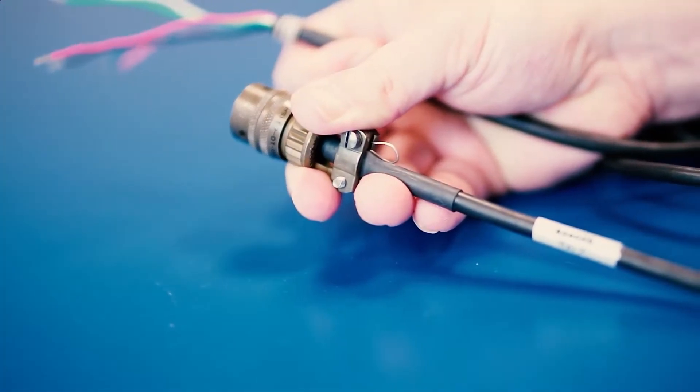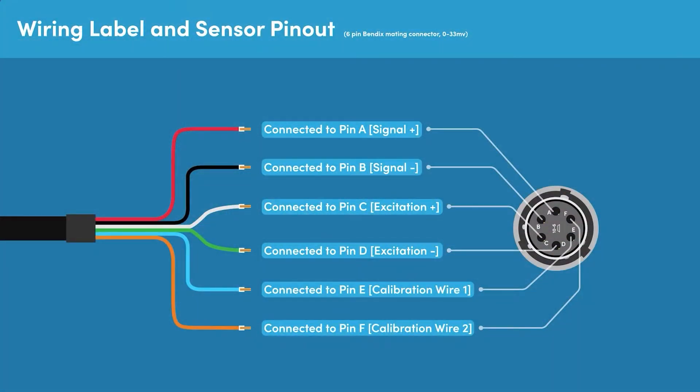The standard connection pinout for a cable used with a pressure sensor that has a 0 to 33.3 millivolt output would be as follows. The red wire is connected to pin A and is signal positive. The black wire is connected to pin B and is signal negative.